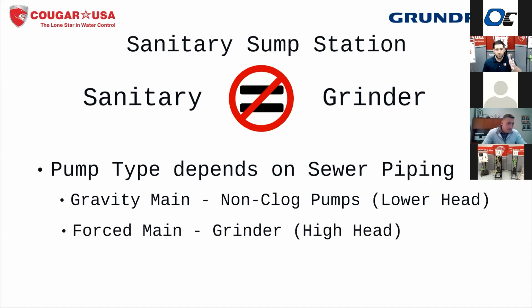When we do the force main is really where we want to move to the grinder. I think you're going to typically see that more in rural applications or anywhere where you have high elevation changes, things like that. City of Houston, we don't have a lot of force main applications. Central Texas and Austin, they do have a lot of force mains. So it really depends more on the municipal piping than on what's in the building. And with the non-clogs, solids typically aren't an issue. We can pass pretty large solids with those Grundfos SL pumps. Okay.